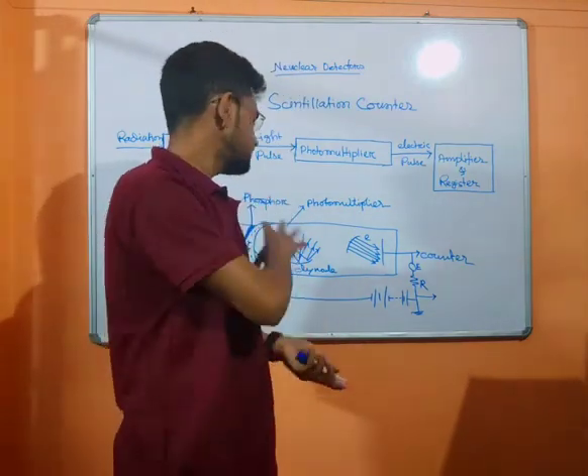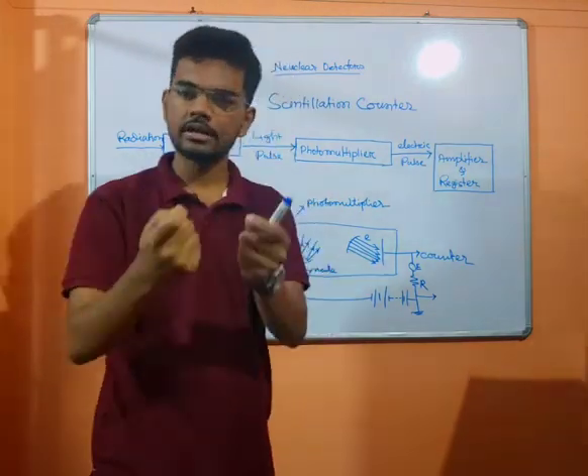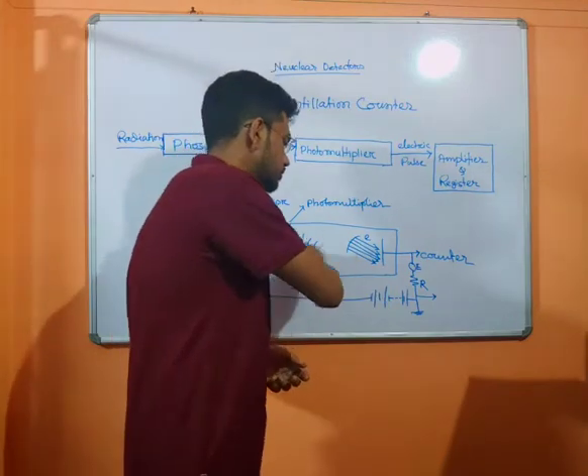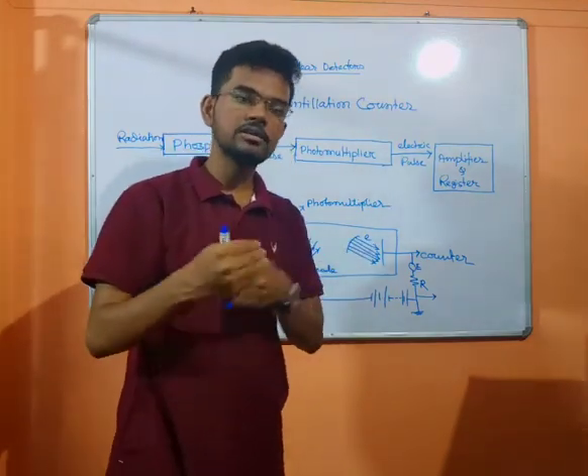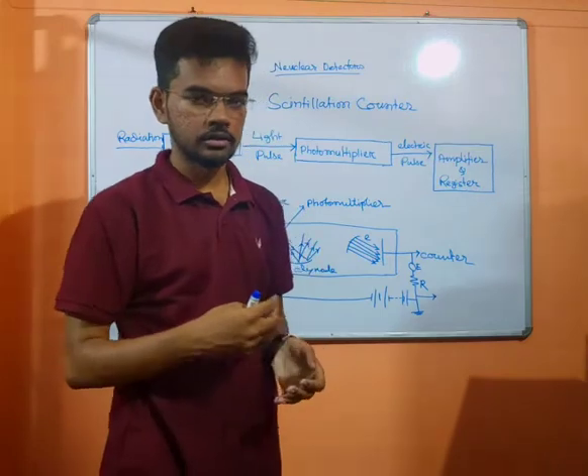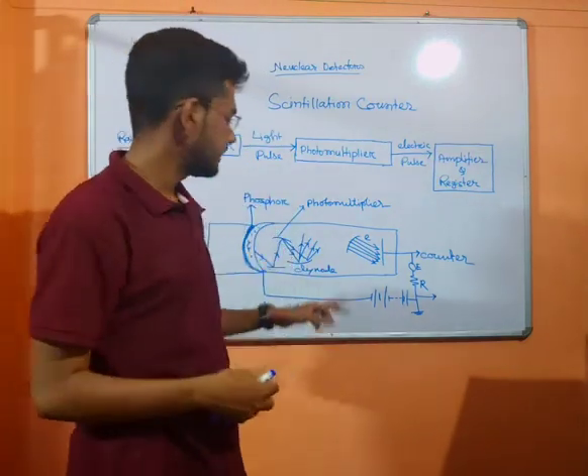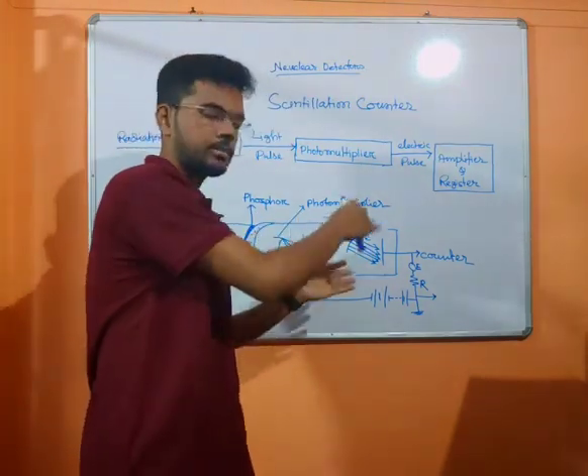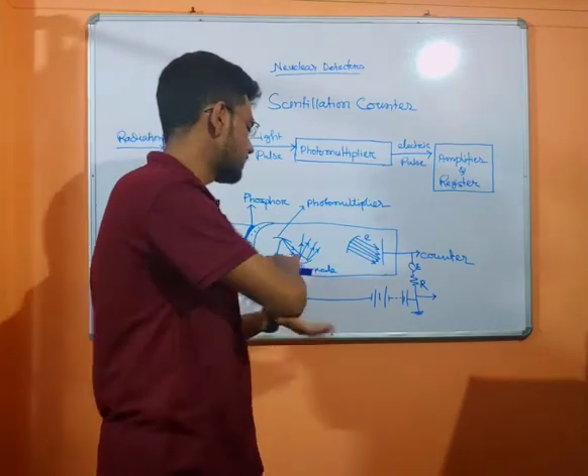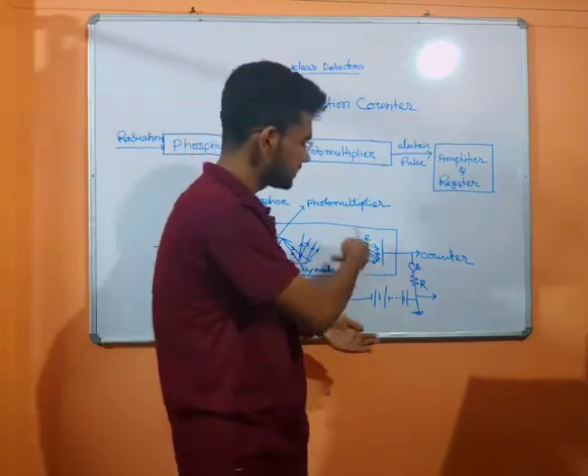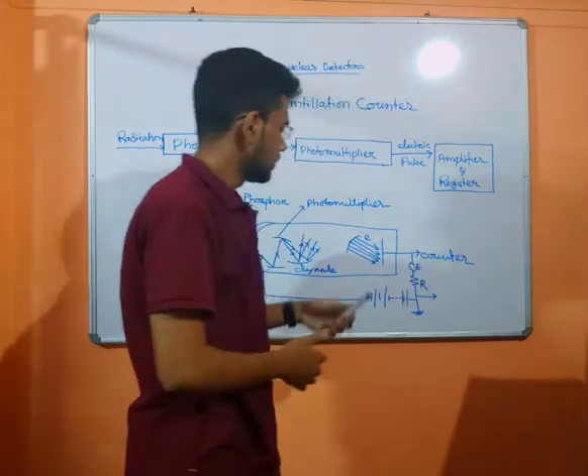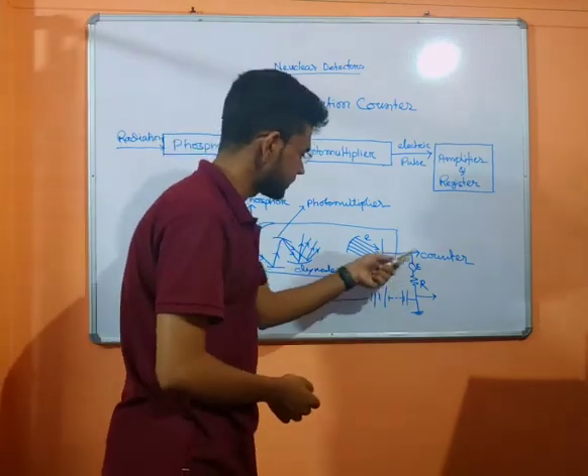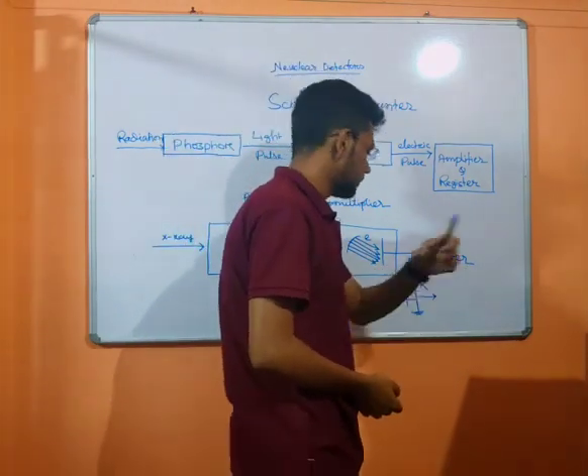Why do we use the multiplier? If you use radiation like a nuclear particle such as an alpha particle, the electric impulse from the plate will need to be strong enough to register. So as a multiplier, we use the dynode. The dynode is the first step of amplifying the electric impulse. The final electric impulse is received by the anode plate, connected to the positive terminal, and is counted.